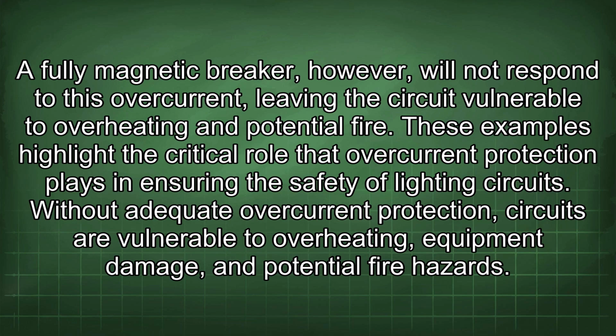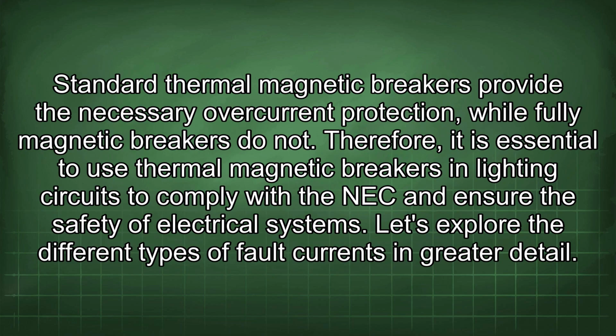These examples highlight the critical role that overcurrent protection plays in ensuring the safety of lighting circuits. Without adequate overcurrent protection, circuits are vulnerable to overheating, equipment damage, and potential fire hazards. Standard thermal magnetic breakers provide the necessary overcurrent protection, while fully magnetic breakers do not. Therefore, it is essential to use thermal magnetic breakers in lighting circuits to comply with the NEC and ensure the safety of electrical systems. Let's explore the different types of fault currents in greater detail.